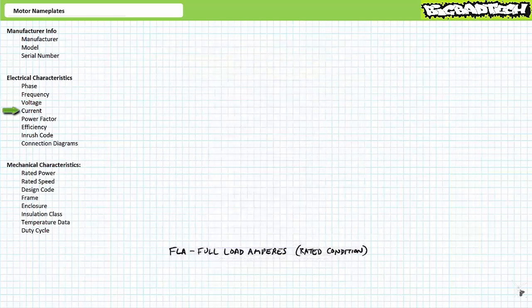Again, I must remind you the current entry on a motor nameplate specifies the amount of current drawn by the motor when the motor is operated at the rated condition, or to use a similar term, fully loaded. For this reason, rated current is sometimes referred to as full load amperes, or FLA. If the motor is underloaded, we might expect line current to decrease, whereas if the motor is overloaded, we might expect line current to increase. Anything in excess of the rated current would therefore be considered an overload condition.